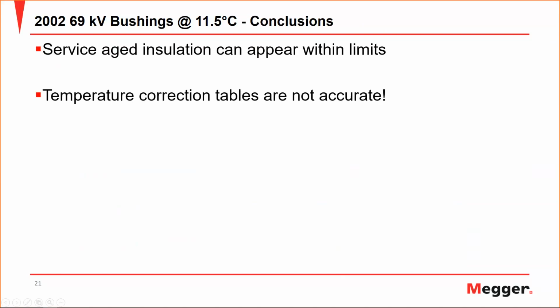We also seen that the temperature correction tables are not accurate. For this one particular bushing, it did not age as expected compared to its sister bushings. So the temperature correction tables are completely out the window and are not appropriate for evaluating this set of bushings or any asset, and that is directly coming from the standard.